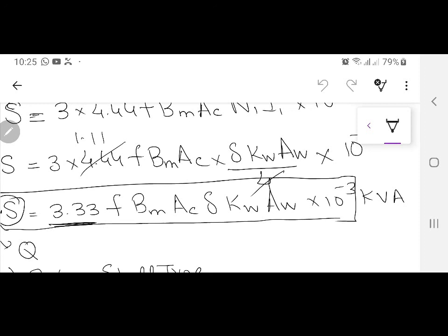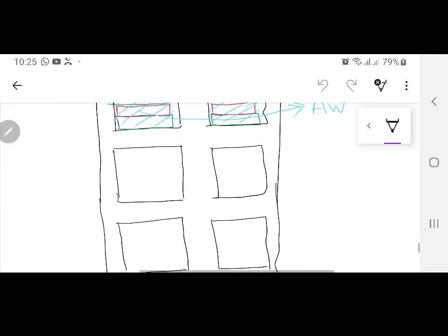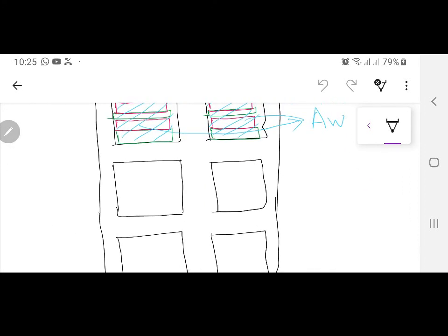So normally when you are designing a distribution transformer you will refer to a core type because you need to cool it down because it has to run 24 hours a day. But wherever you want more output and you are not concerned with the heating of that core or the material used inside it, because you can cool it down with some forced cooling, oil cooling or air blast cooling, then you are going to refer towards your shell type transformer because it is going to give you a better advantage as compared to your core type.